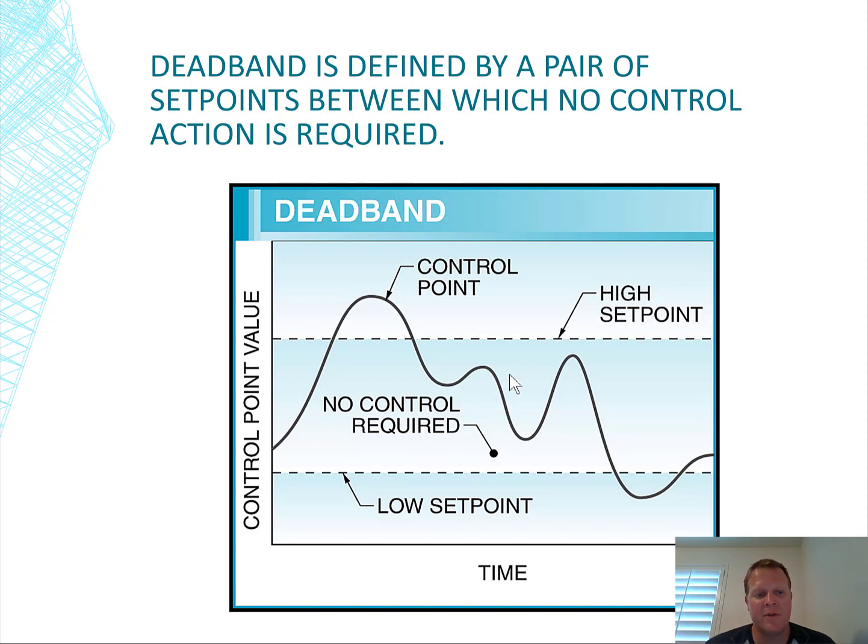As long as people feel comfortable from 74 all the way to 70, or 70 to 74, and that feels comfortable, it's not a big deal if it's not right at 70 or right at 72. 70 to 74 feels pretty good. So you could expect some modulation in there, where only when the sensor is reading outside of the acceptable parameters does it actually do something. So that's just an idea that we could bring up. I wanted to share that as well.